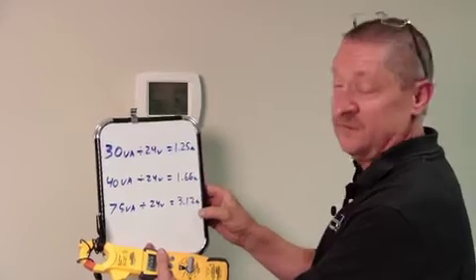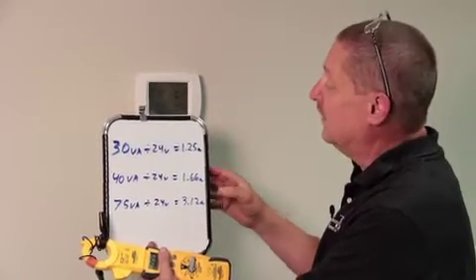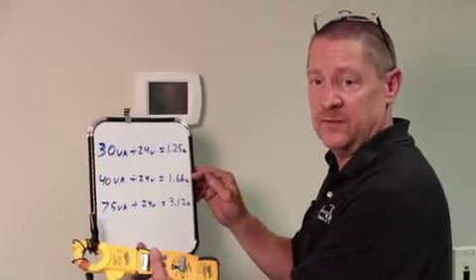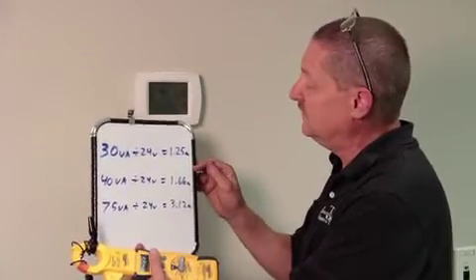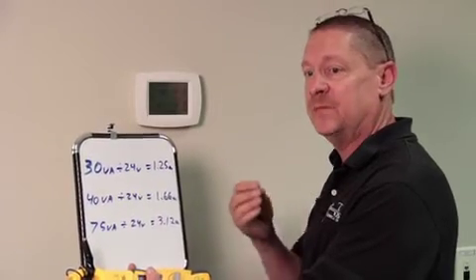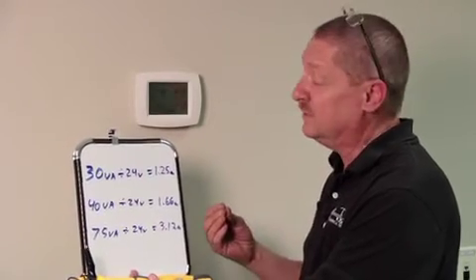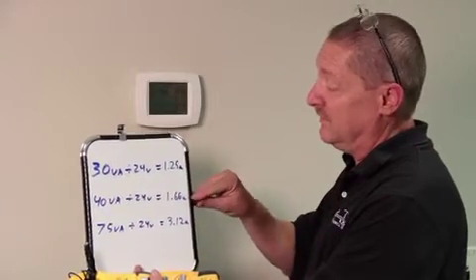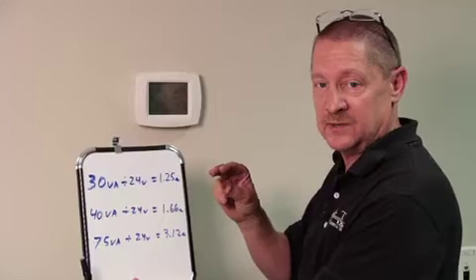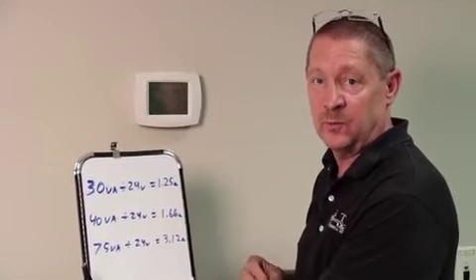A 40 or 75 VA is for an air handler. You can see these numbers are a lot smaller than the fuse size. The fuse on these is about 3 amps - that's because of inrush current. It can handle that inrush, but if I got a short circuit or overloaded condition somewhere between the amp draw of the transformer and the fuse protection, I could actually burn out that transformer without blowing the fuse.